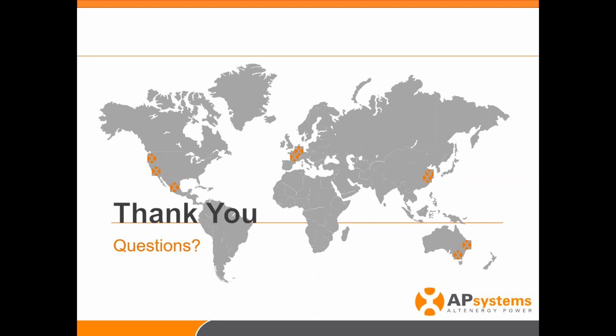So that's a good question, a great question, actually. So no, the answer is, if there's no power to the ECU-R, there is no record of that information, because the ECU-R needs to be powered to be able to go out and inquire to the inverters, basically ask the status. They need to go out and say, what is your status, every 5 minutes. If the ECU-R is not powered, that will never happen. If it loses internet connection and the ECU-R is still powered, we will hold that data. So that's the key piece right there. No power to the device, no data. Power to the device, but no internet, the information is being held, waiting for the internet to be reapplied to push that data back to the cloud.